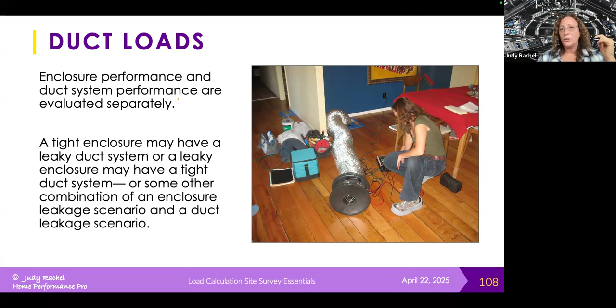There you could have a leaky enclosure and a tight duct system, and you can have everything in between. So if you're going to use an existing duct system, you definitely need to do duct leakage testing. If you are installing a new duct system, then you need to get a sense from the contractor whether they only do code minimum work or whether they do better, and come up with what the duct leakage is expected to be of that system.